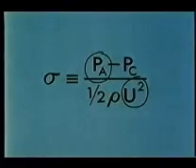We have seen what cavitation looks like, have learned about some of its effects, and examined some of its features as it develops. Pressures near the vapor pressure require the presence of nuclei, which contain minute amounts of vapor, gas, or both. Cavitation will occur only when these nuclei become unstable and grow when subjected to a pressure reduction.